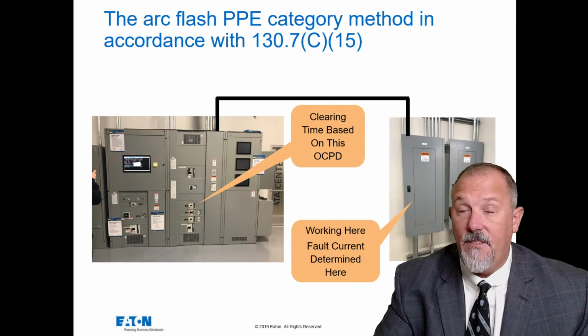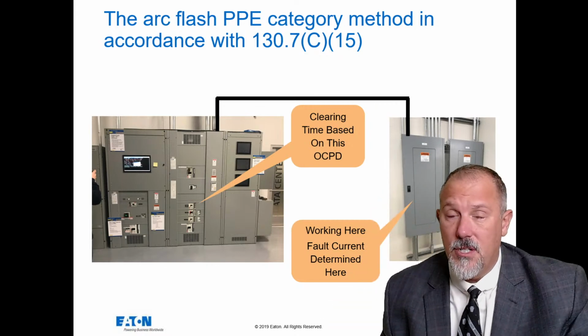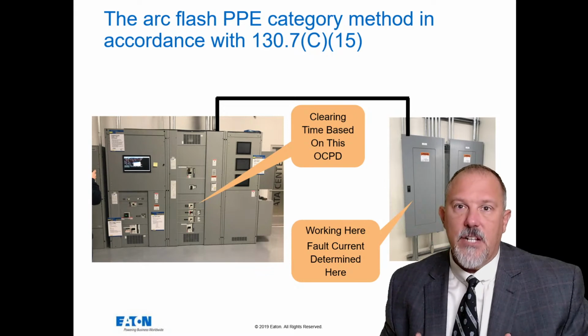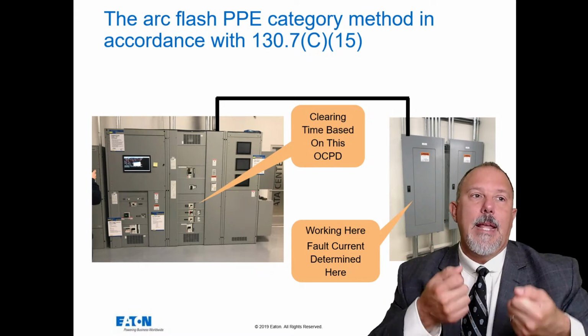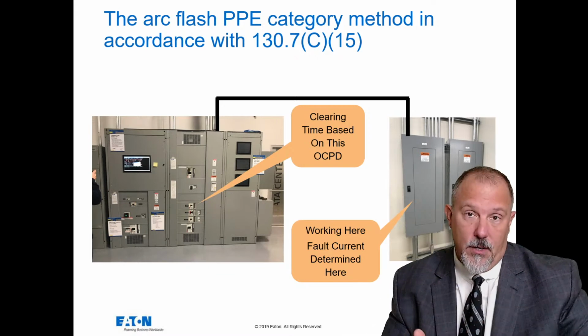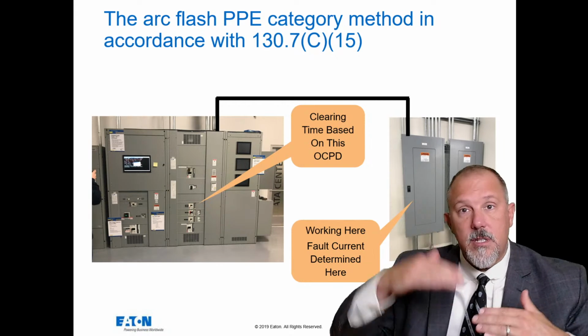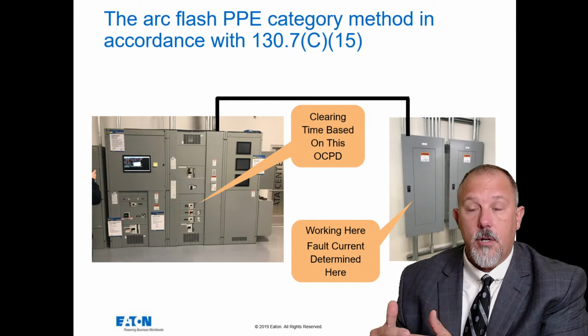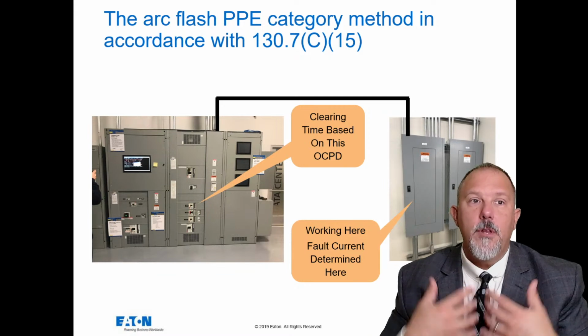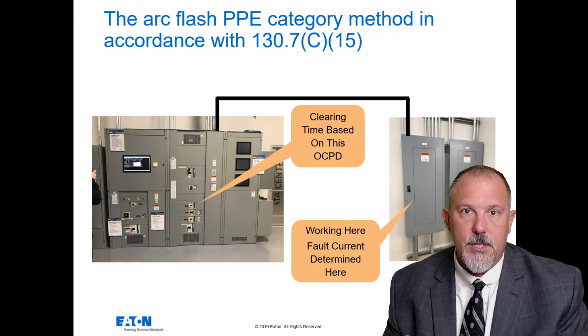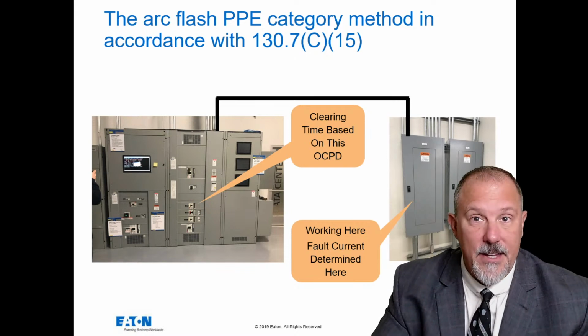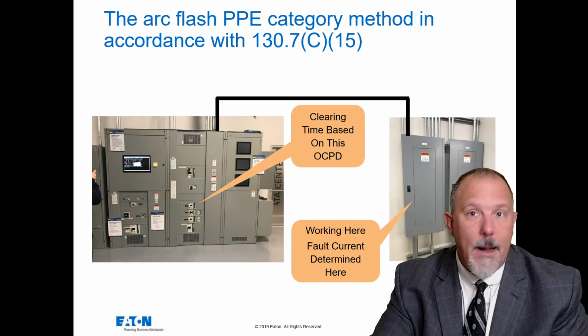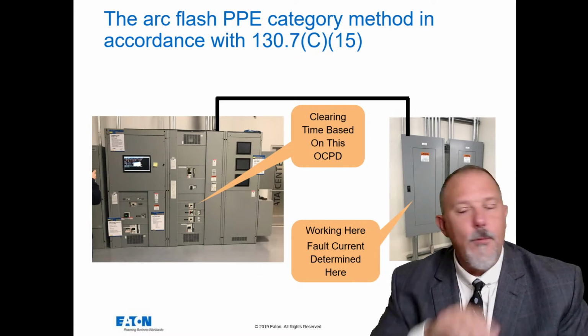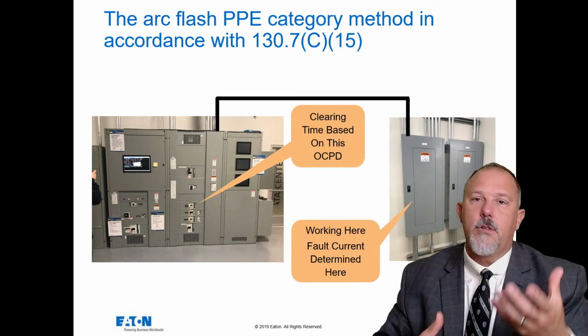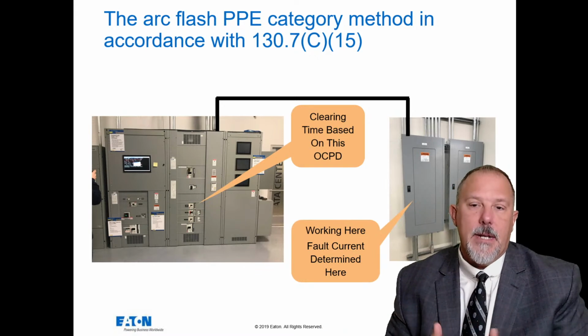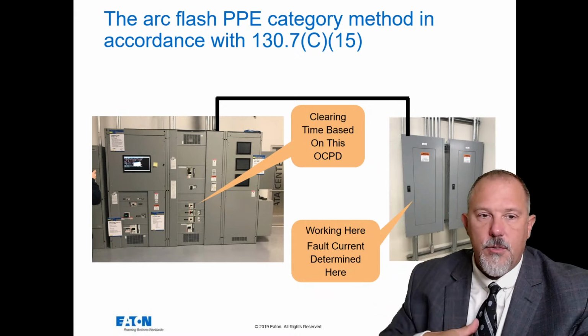And why is that important from a safety perspective? Is it just because it takes me time to dress up? No. When I'm in a 40 cal outfit trying to operate probes, it can be clumsier. It can be more difficult. If I can reduce the severity for the electrical worker, then I can put the worker into a more flexible dress so that it's easier and less likely for them to make a mistake or drop something because of the gloves or whatnot. And then we'd have a whole different debate on the gloves, the dexterity, all that other good stuff. But in any case, I can get you into a lighter dress.